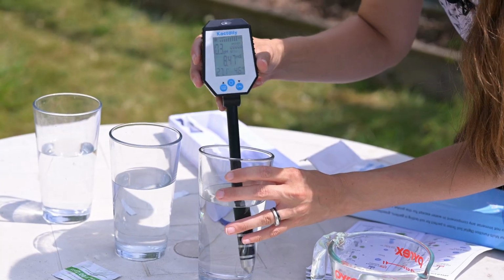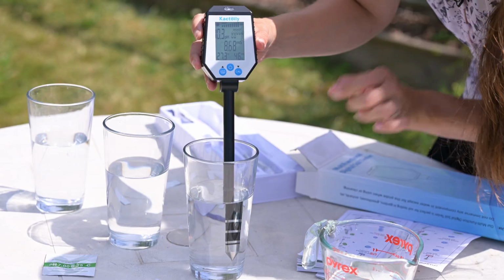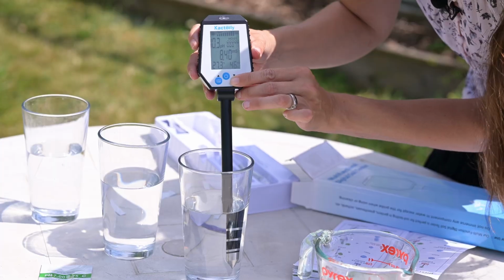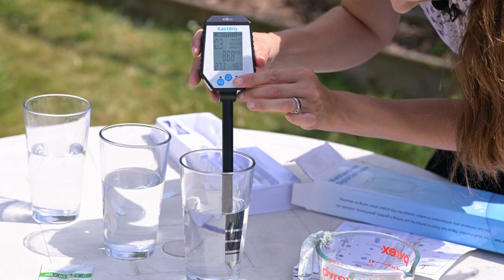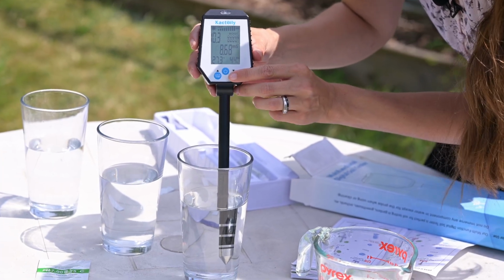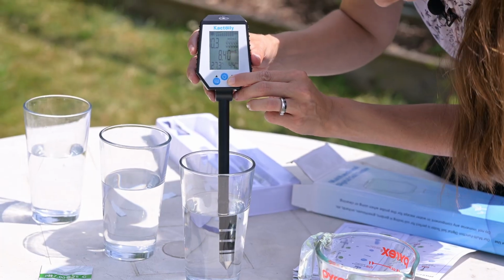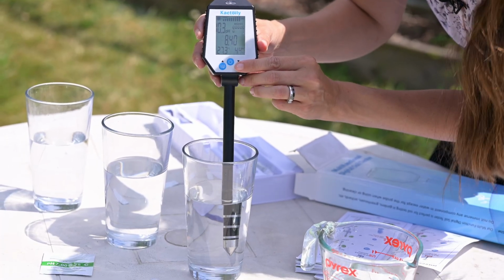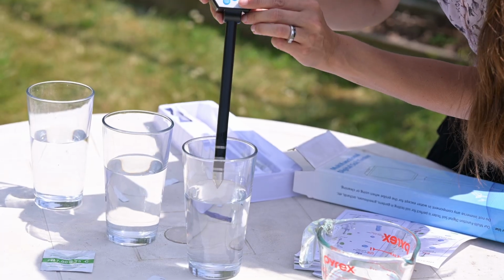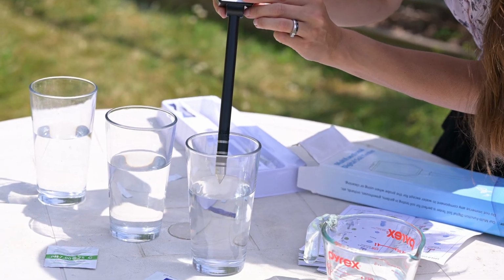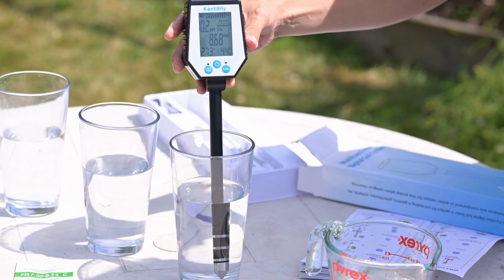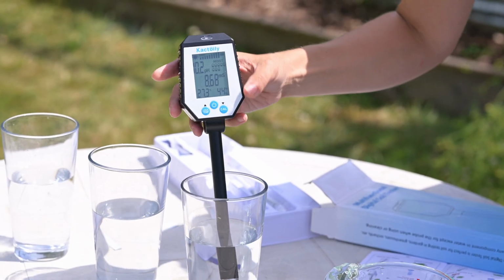I am feeling willing to accept a 10.3. Close enough! Whatever. We're gonna hit calibrate. pH is blinking. 1, 1,000, 2, 1,000, 3, 1,000. And then press it. It's supposed to blink to a 7. You're not blinking to a 7. Makes no sense. I know, I took you out because that seemed to work the last time. Did not blink to a 7.